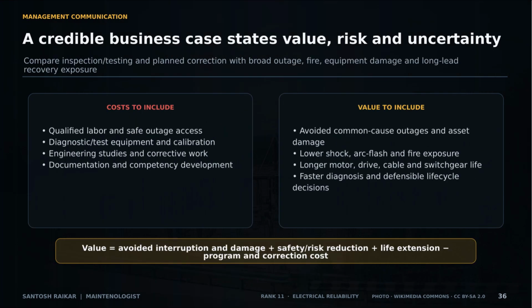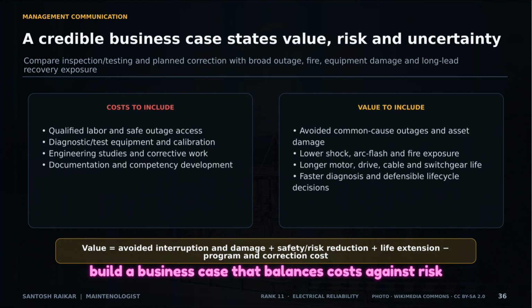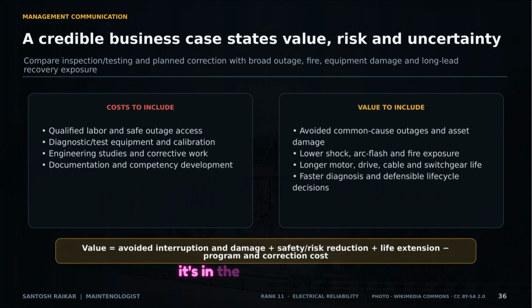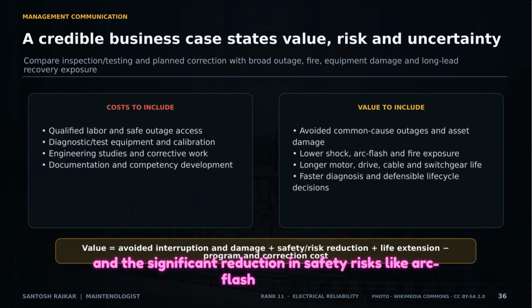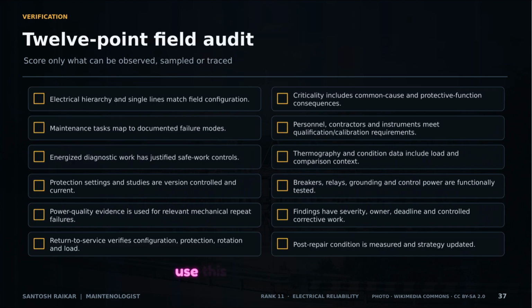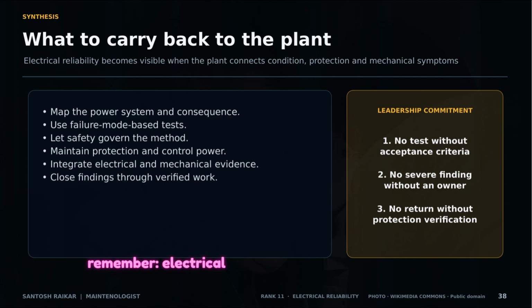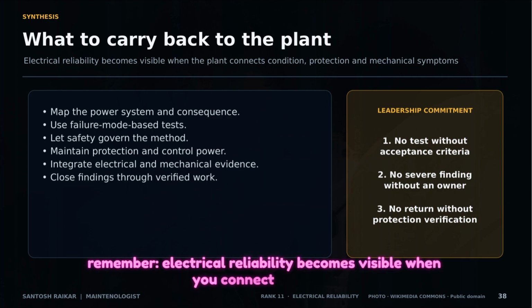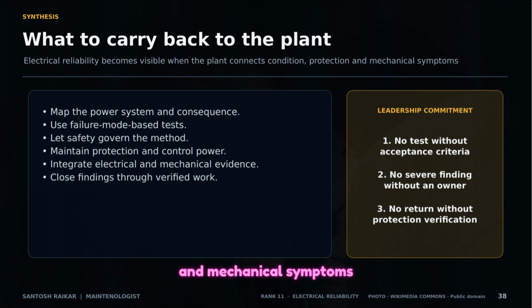When talking to management, build a business case that balances costs against risk. The value isn't just in the repairs. It's in the avoided outages, the extended life of cables and gear, and the significant reduction in safety risks like arc flash and fire. To maintain the program, use this 12-point field audit. Score only what you can actually observe or trace. If your hierarchy doesn't match the field configuration, or if your protection settings aren't version controlled, you have work to do. As you head back to your plants, remember, electrical reliability becomes visible when you connect condition, protection, and mechanical symptoms. Commit to no tests without criteria, no findings without owners, and no returns without verification.